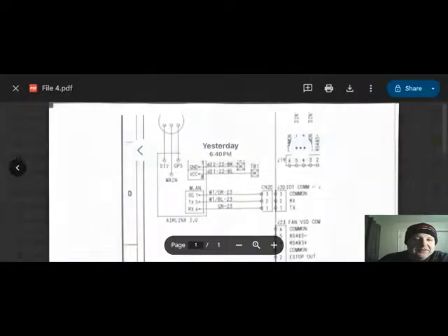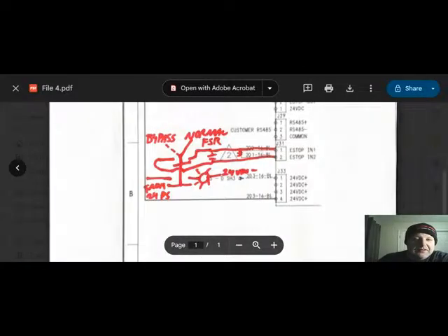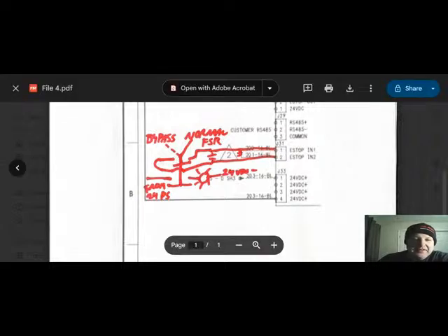Again, I'm going to put this 2-position switch in here. These are both going to be open when we're in normal. So we're relying on our fire suppression relay to latch this circuit. And when we switch this to bypass, this contact is going to make. Our circuit is now maintained by the manual switch. And then this circuit is going to make.